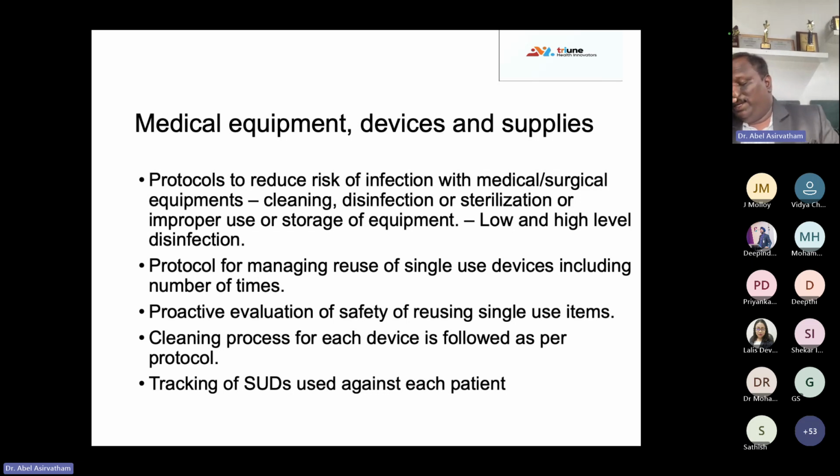Okay, but whenever SUDs are being reused, one is the number of times, and second is we need to give them a different ID each time, and the same needs to be documented in the patient record also for retrospective tracing. Okay, so it's very, very important. This was completely checked. And one more important thing you do is about integrity check. Before using an SUD, you do a proper integrity check. Like for example, if it is a guide wire, is there any kinking, any stain, those kind of things need to be taken into account.